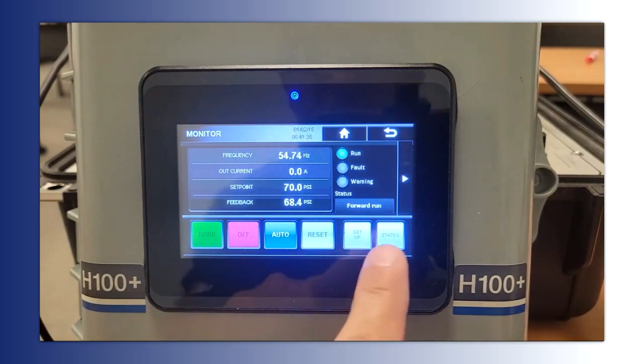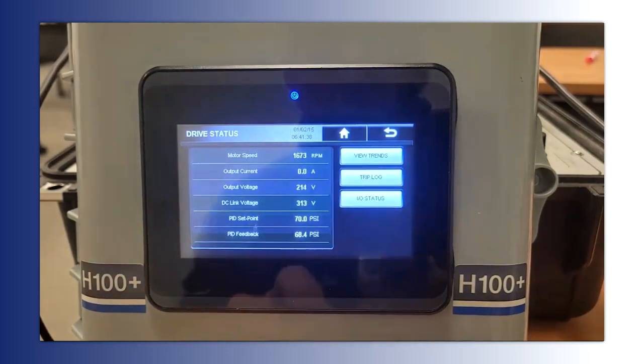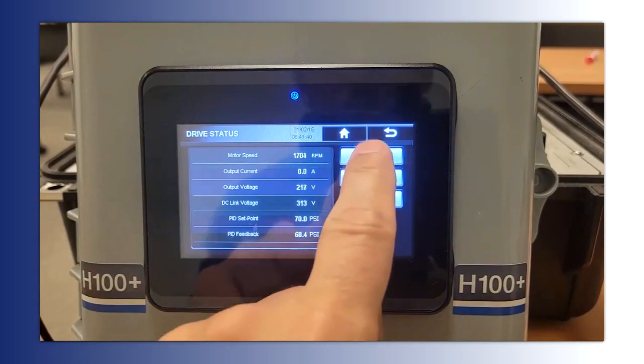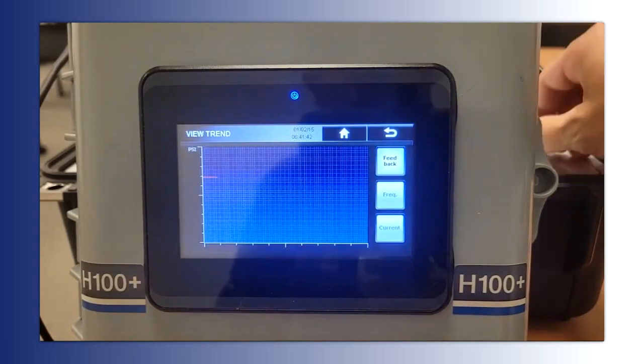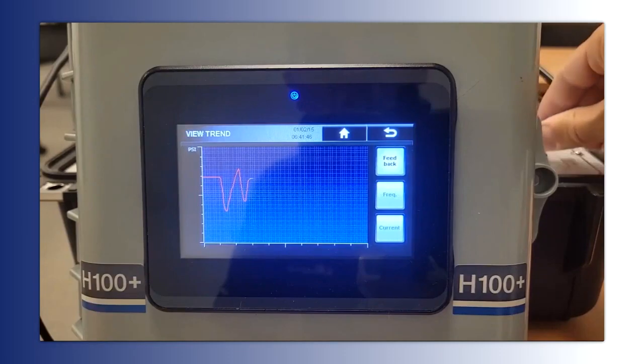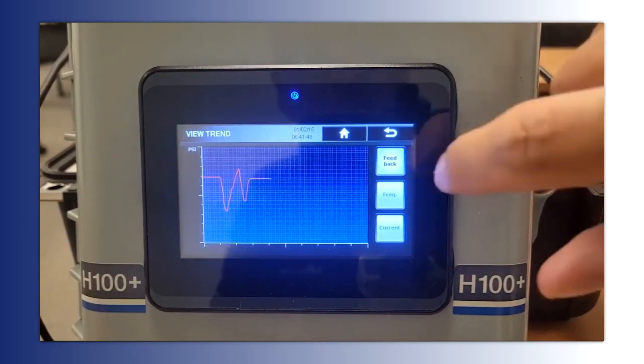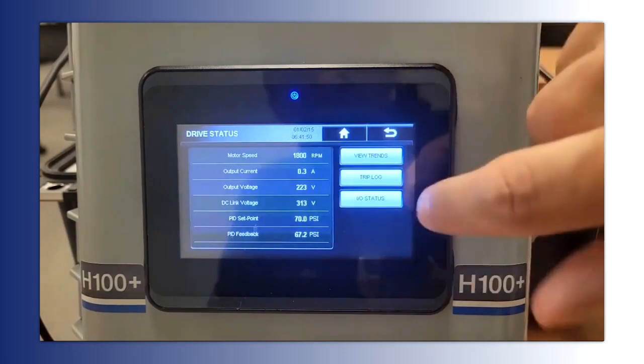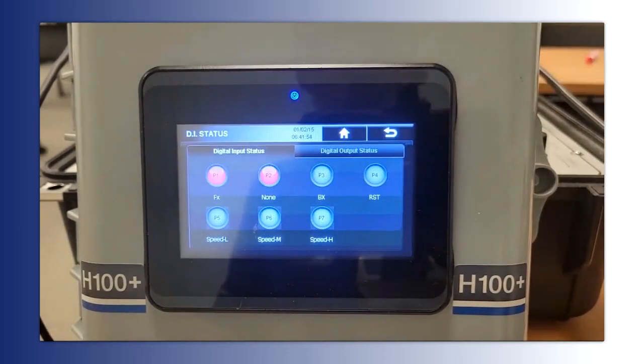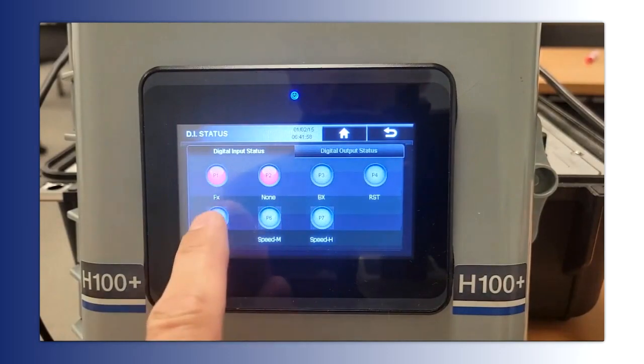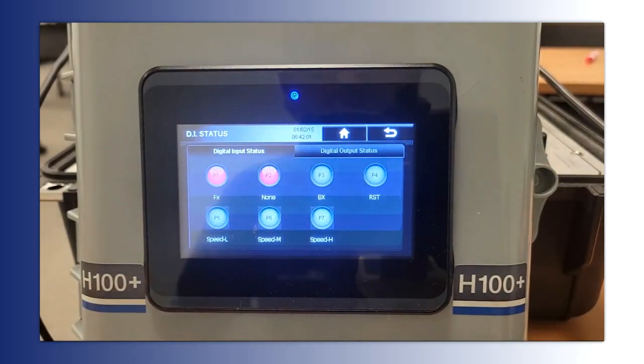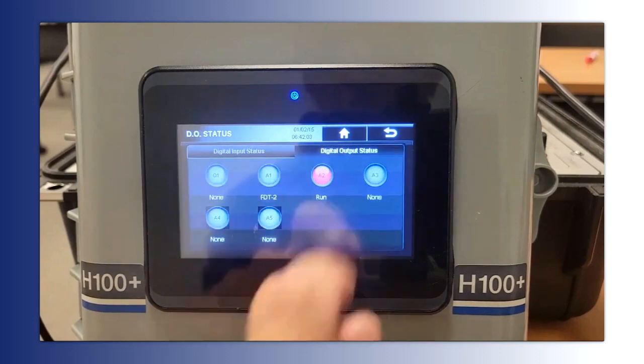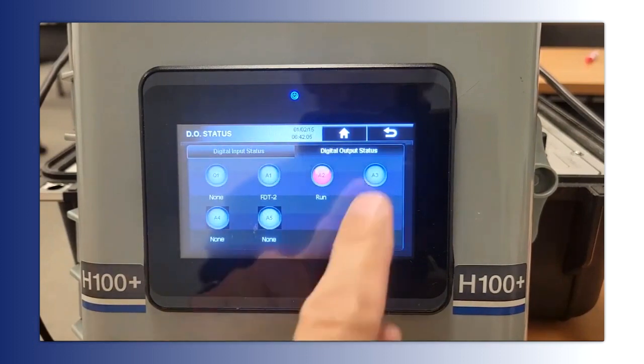Some other things we could see are in status. So we have trends. You could see your feedback go up and go down. Okay. You could also see frequency and current if you click those. Another thing you can see in status is your I/O status. So right now I actually have my P1 and my P2 on. My P2 is set to none. P1 is FX, which is a forward run. That's my run command. I could also see my output status here with these little LEDs on here.